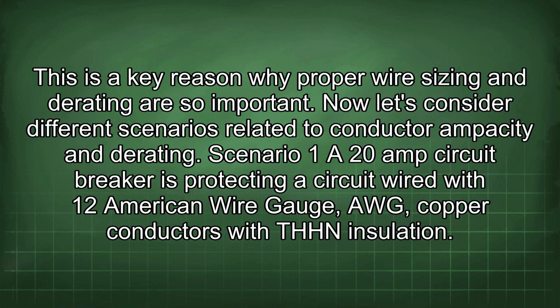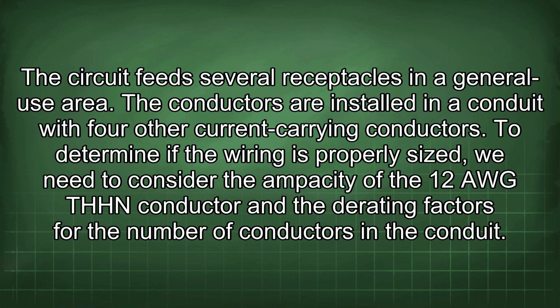Now let's consider different scenarios related to conductor ampacity and derating. Scenario 1: a 20 amp circuit breaker is protecting a circuit wired with 12 American wire gauge (AWG) copper conductors with THHN insulation. The circuit feeds several receptacles in the general use area. The conductors are installed in a conduit with 4 other current-carrying conductors. To determine if the wiring is properly sized, we need to consider the ampacity of the 12 AWG THHN conductor and the derating factors for the number of conductors in the conduit.